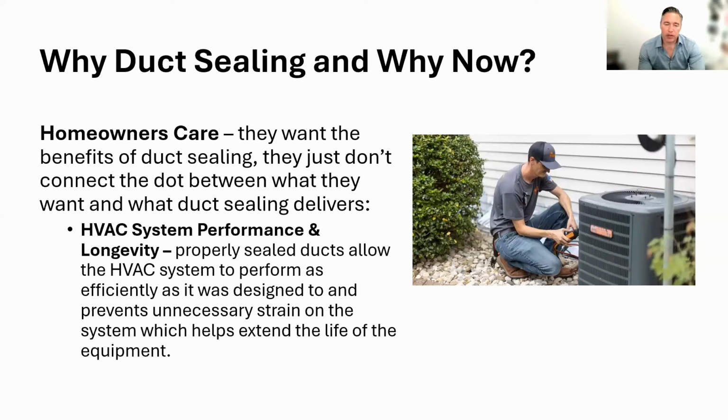So if you break your utility bills down to just heating and cooling, the differences of the energy being consumed to heat and cool your home, what we're seeing consistently is right around a 15% reduction when you seal that ductwork when it's in the conditioned space. So when the ductwork is 100% in the conditioned space, or running in your conditioned basements or floor cavities or wall cavities, but all inside the house, or better put the envelope, so inside the insulation and air sealing. When that ductwork's running outside the conditioned space, we're pretty confident in saying it's 20% or more in terms of seasonal utility savings. I hope that answers the question.